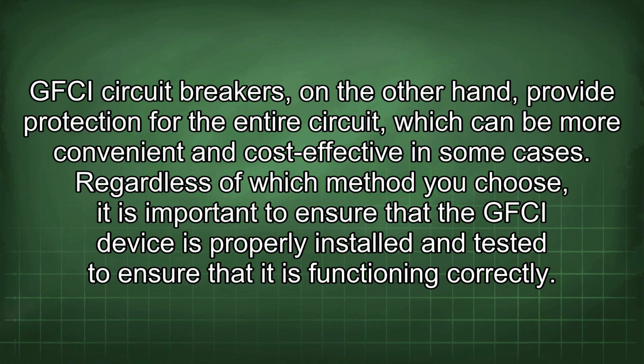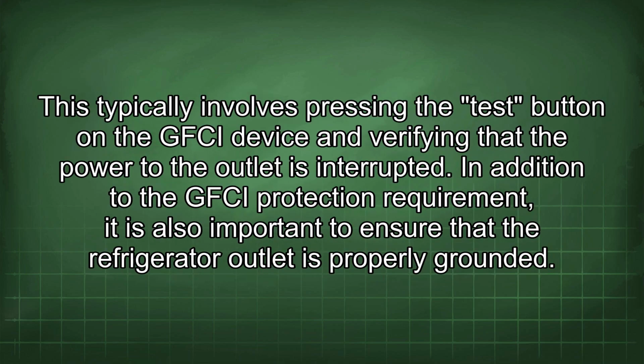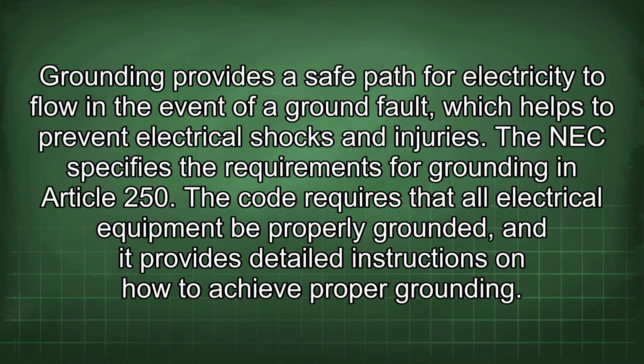Regardless of which method you choose, it is important to ensure that the GFCI device is properly installed and tested to ensure that it is functioning correctly. This typically involves pressing the test button on the GFCI device and verifying that the power to the outlet is interrupted. In addition to the GFCI protection requirement, it is also important to ensure that the refrigerator outlet is properly grounded. Grounding provides a safe path for electricity to flow in the event of a ground fault, which helps to prevent electrical shocks and injuries.